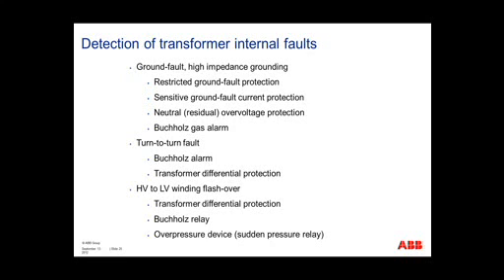For turn-to-turn faults, these are faults between the winding itself. We have our Buchholz alarm and transformer differential protection. With the introduction of microprocessor relays, we also have a negative sequence differential, which we'll discuss later, that can identify these turn-to-turn faults. For high voltage to low voltage winding flashover, we have our transformer differential protection. We'll see it, and so will our Buchholz and our SPR, our sudden pressure relay.